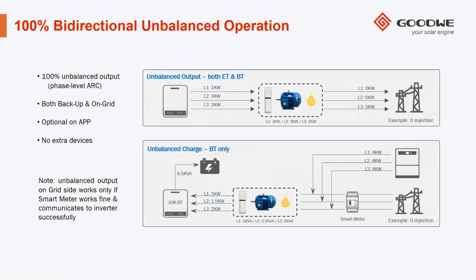As Stephen mentioned before, we have 100% bidirectional unbalanced operation with our ET inverters as well as our BT inverters. What that means on the grid tie side as well as the load side, but more importantly the grid tie side, because not a lot of companies have this, you'll see that the unbalanced output is 100% to ensure that 0 is used from the grid. On the grid tie side, you'll see we can run 1 kilowatt, 3 kilowatt, 2 kilowatt. It's very easy for the inverter. Even if you don't have batteries connected to our ET inverters, they are able to do this. So it's great for domestic residential installations where balancing the loads are generally not an option.